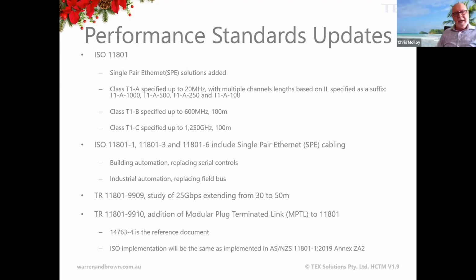Some of the things covered: ISO 11801 covers single pair Ethernet solutions, which has been added in now. Class T1A is specified up to 20 megahertz with multiple channel lengths based on insertion loss specified. So you've got different levels there: 1,000, 500, 250 and 100.